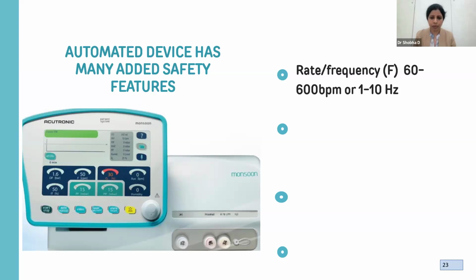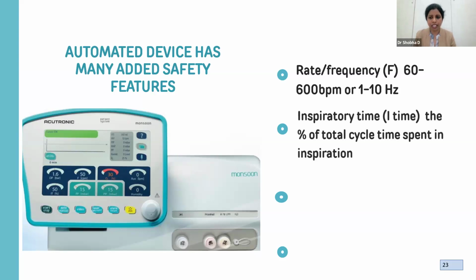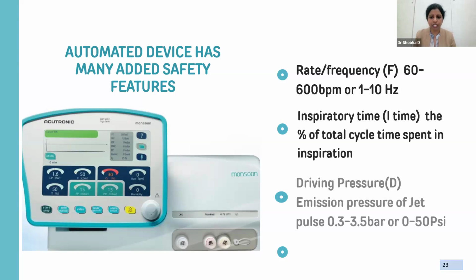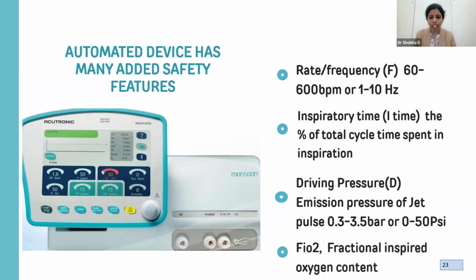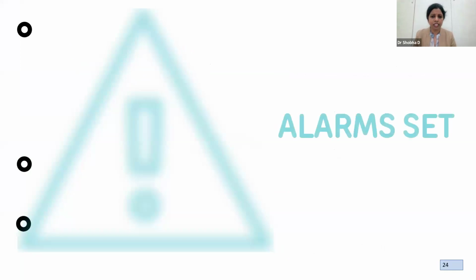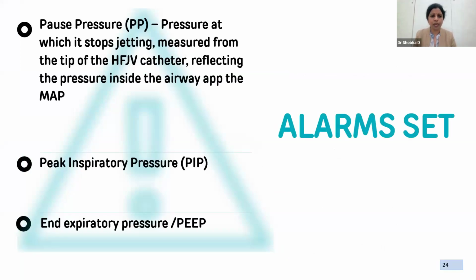Otherwise, it's breaths that we put for jet ventilation. The inspiratory time is the percentage of the total cycle time spent in inspiration. Driving pressure is the emission pressure of the jet pulse, 0.3 to 3.5 bar. And the FiO2 depends on the entrainment of the oxygen, so what we set will be different from what the patient receives. We are also going to set the alarms. We have the pause pressure, which is the pressure at which the ventilator stops jetting. It is measured from the tip of the high frequency jet ventilator catheter, which reflects the pressure inside the airway and approximates the mean airway pressure. We also set the peak inspiratory pressure and the end expiratory pressure, or PEEP.